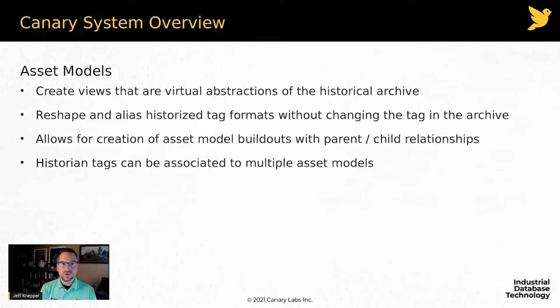Those SCADA tag names could be great for a local site operation, but very problematic if I'm trying to create a corporate naming standard and I have sites that don't match that standard. I don't have to change the way those tags are being logged to the historian — instead I can use Views and create rules that alias those tags so I can interact with the data according to my corporate standard.